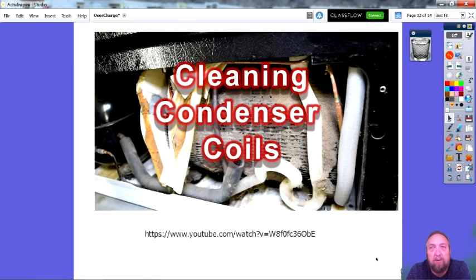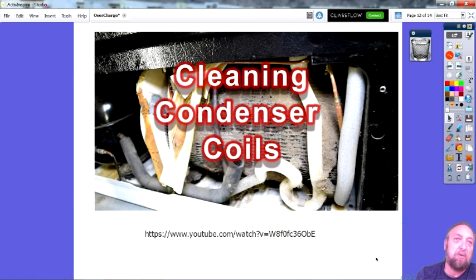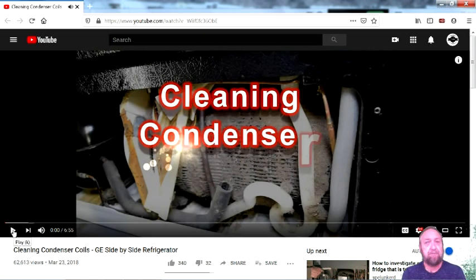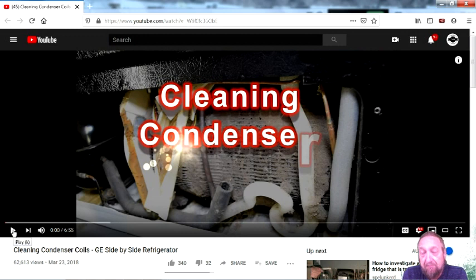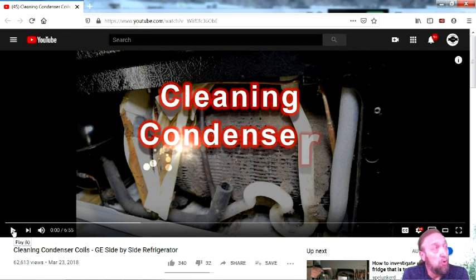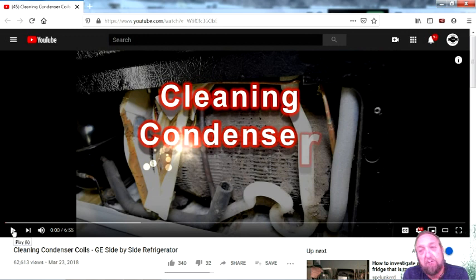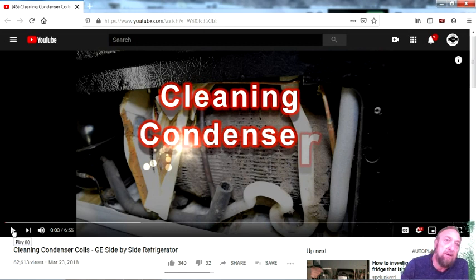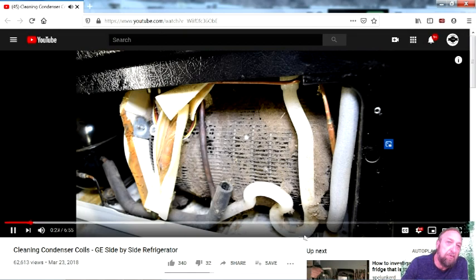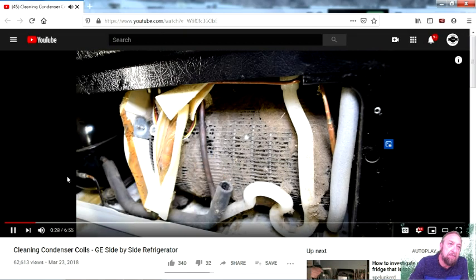Cleaning condenser coils — you can have dirty condenser coils just like a dirty evaporator. A refrigerator condenser coil can be dirty from dust, dog hair, cat hair and needs cleaning. If the condenser is dirty, it will not effectively dissipate the heat. If it can't get rid of the heat, the pressure goes up, temperature goes up, and you might increase your subcooling — too high a subcooling. We need to dissipate the heat, so we need to clean these coils.